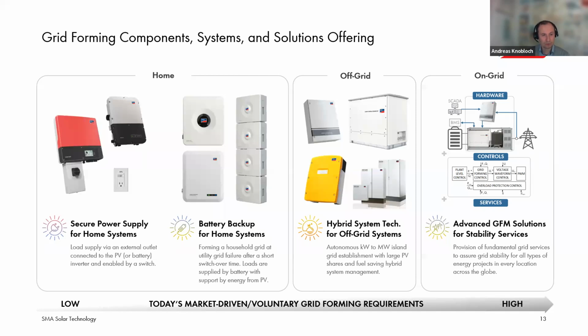Then included in our offering are also hybrid system technologies for off-grid systems that enable autonomous island grid establishment in the range of kilowatt to megawatt with large shares of PV. And we have also fuel-saving hybrid system management solutions that enable saving any form of fuels.